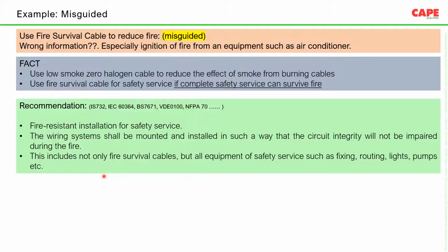They put higher quality wire. But you should understand that if you put a wire in a cable tray and the cable tray is not withstanding the fire, what is the purpose of putting a fire survival cable? If you put the wire through a conduit and the conduit is plastic and starts melting, then what is the purpose of fire survival insulation? If the switch has burned, or the junction box completely burned out, what is the purpose of using fire survival cable?